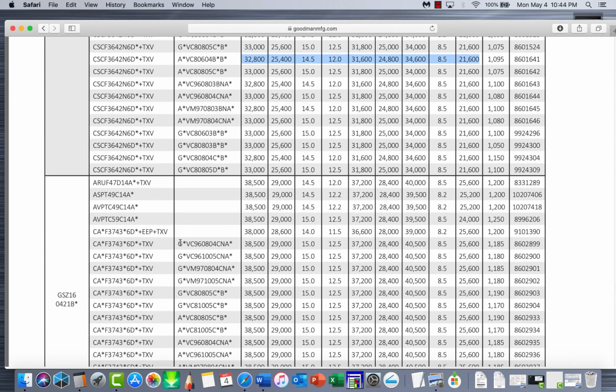So that's why I said moving down to a unit like this one here, this meets and exceeds our demands. This will stay in low speed. Extreme weather, 40,000 is going to help out a whole lot more. 29,000 meets our demand. 38,000 way up above it. So this would be the outdoor unit. And this would be your indoor coil, the TXV. And this would be your furnace right there. And that's how you size up the piece of equipment based off your Manual J load.